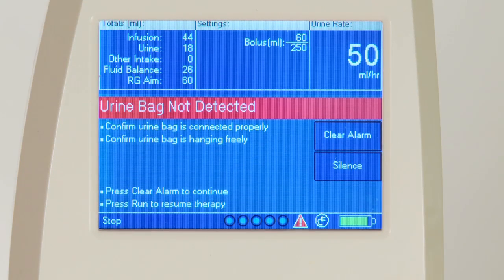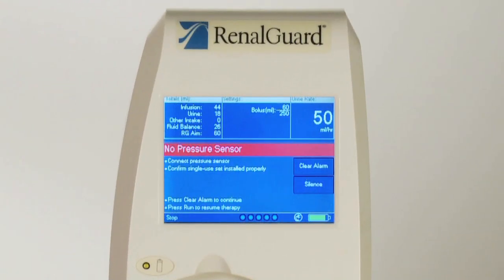Urine bag not detected. Ensure the urine bag is on the hook. No pressure sensor. Ensure the pressure sensor is connected. If the pressure sensor is connected, open and close the door. System fault. Turn the console off and then back on. If the fault repeats, remove the console from service.